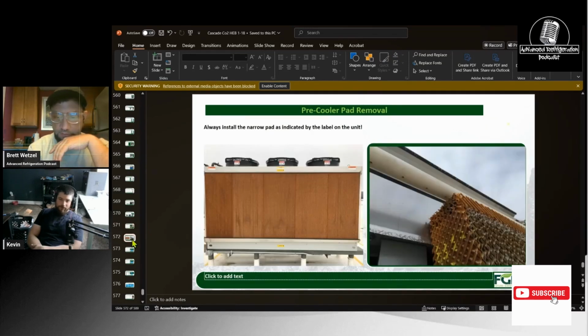So these pads are incredibly heavy when they're wet. Oh, they suck, dude, when they're wet. Even though it went through its rinse cycle for however long when the fan's still running, they were still swollen. So we had to take it out because we had to prove that post-pad temperature sensor is basically somewhere behind here. And as you can see, this is about the same size. This one will be a little bit different. The one that's going to be different typically has yellow paint at the top, telling you that's the first one to go in.